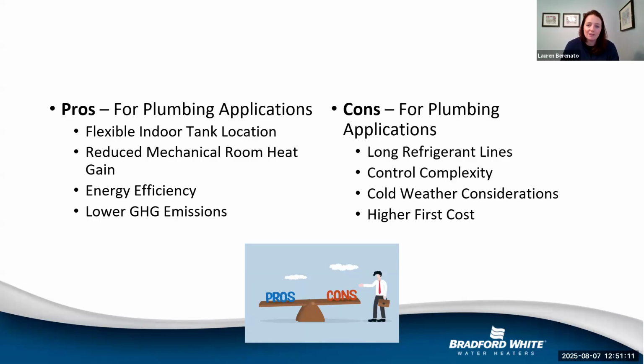You've got your cold weather considerations in colder climates. The outdoor unit would require a defrost cycle or backup heat. And it does have that higher first cost. I think that's one of the things that has been sticker shock to building owners: why am I paying this much more money for this water heater when electric would just do the same? But for overall carbon emissions, the heat pump will have much less overall carbon emissions.